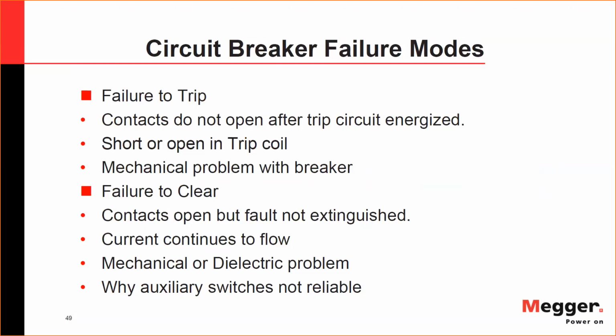The spring was not charged enough, or it was loose, or something was wrong mechanically with the mechanism itself, so that it did not operate correctly. This is what we consider a complete failure. It didn't operate at all.